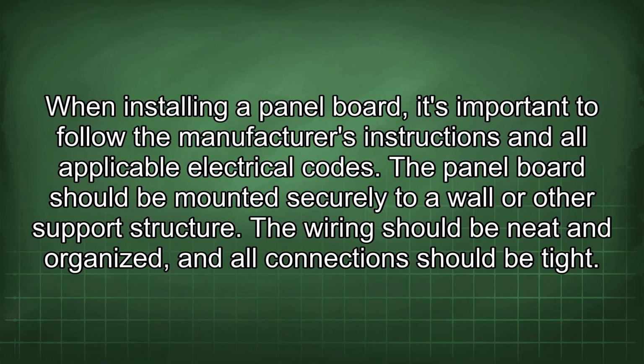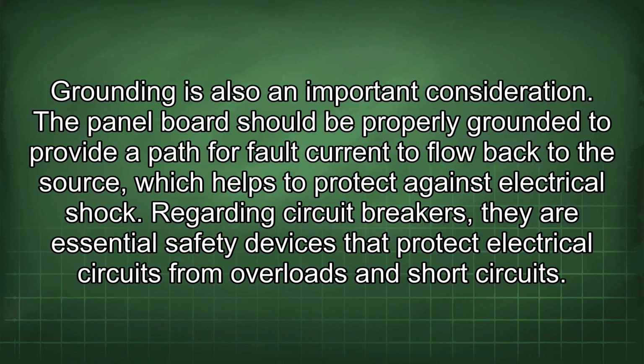When installing a panel board, it's important to follow the manufacturer's instructions and all applicable electrical codes. The panel board should be mounted securely to a wall or other support structure. The wiring should be neat and organized, and all connections should be tight. Grounding is also an important consideration. The panel board should be properly grounded to provide a path for fault current to flow back to the source, which helps to protect against electrical shock.